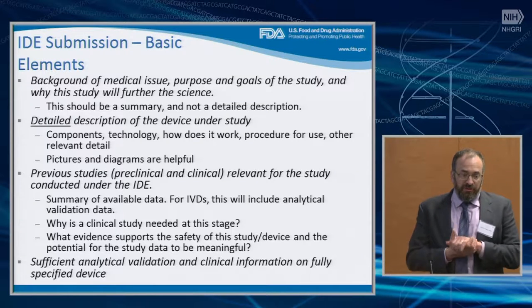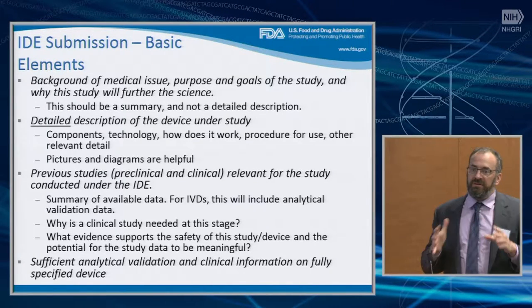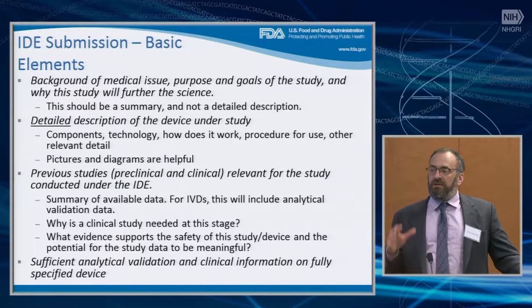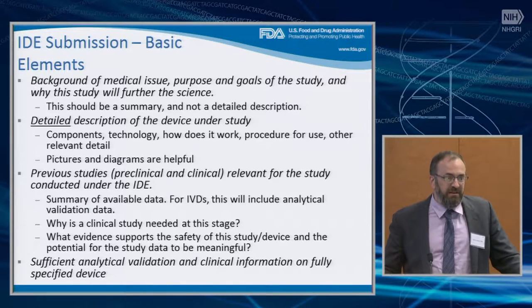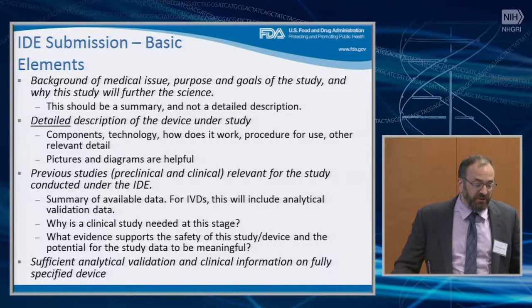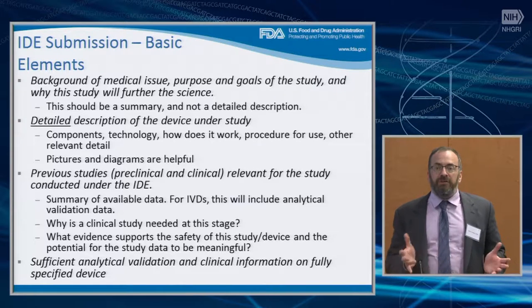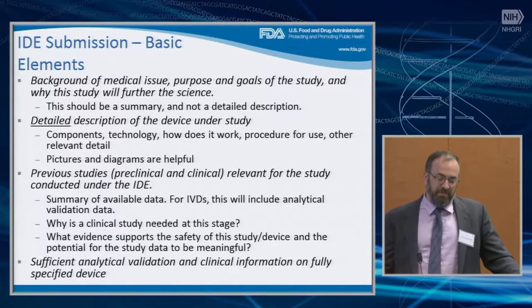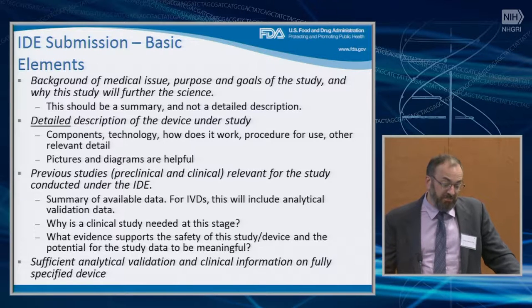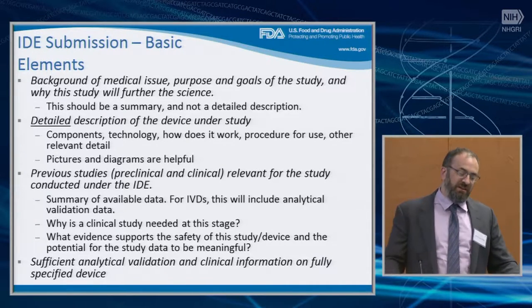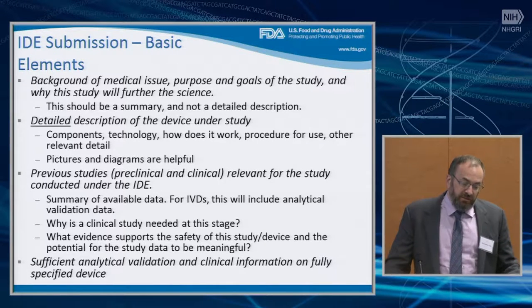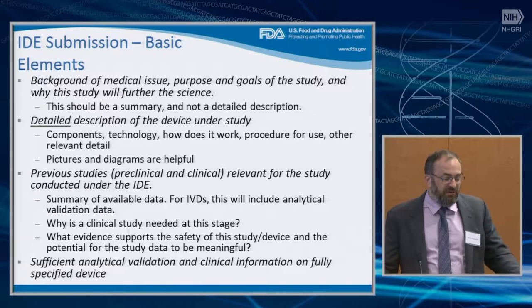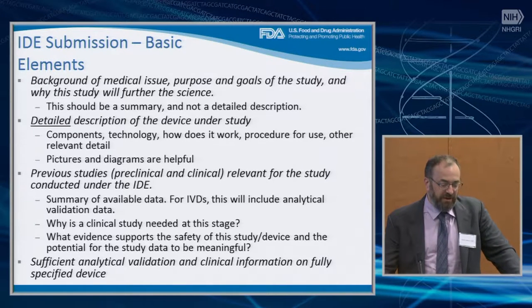I wanted to run through the elements outlined before and give a few tips, because figuring out what information to send to FDA — especially the first time you're doing an IDE, but even later — can be confusing. You do need to describe why you're doing the study, but this is not an R01, so it doesn't need to be a full justification of a hypothesis — more of a summary, like an abstract. We want to know why you're doing the study and what the motivation is. A detailed description of the device under study — we want to know all the components and how it works, and to the degree you can illustrate things in pictures and diagrams, that's very helpful.